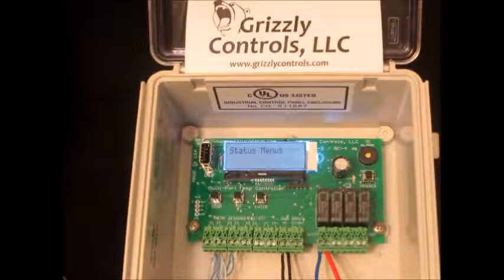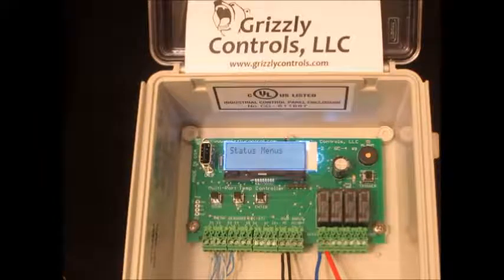It has an onboard real-time clock, and you can use it to control things based on the time of day. So if you want something to turn on at 6 a.m. and turn off at 6:30, you can use a control rule to do that. You can also combine controls, so I could combine a timer control rule with a differential controller, for example. And any combinations you want, it's very configurable.